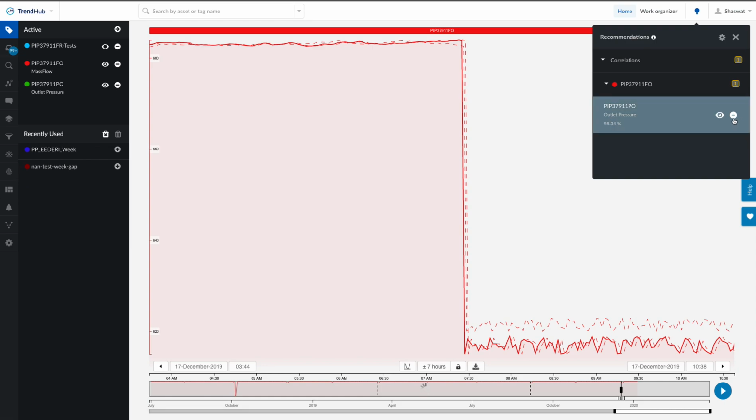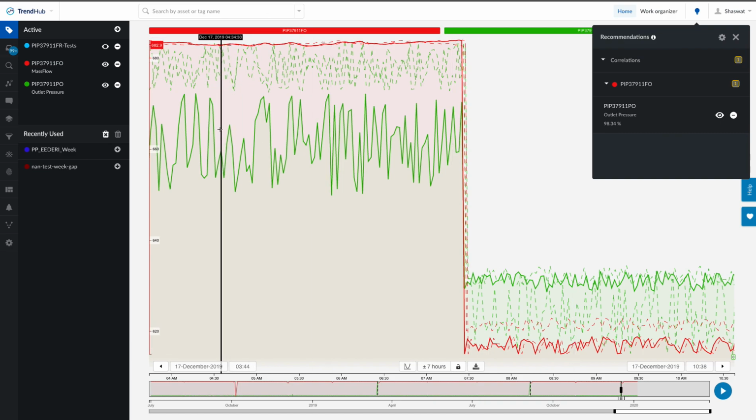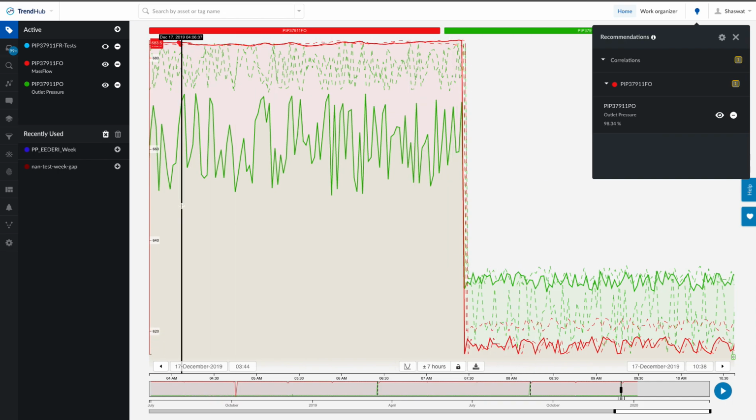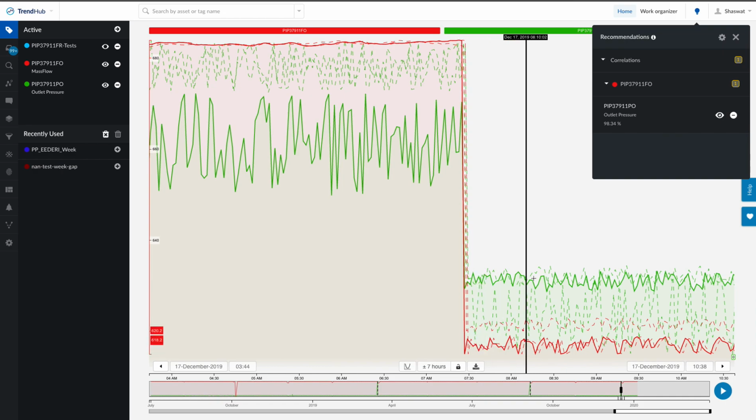So I can bring this pressure here. And as I bring the pressure, you can see in the two events, pressure was a little high and then it dropped kind of low. Versus the third event, we had little lower pressure, and then when it dropped because of the leak, it didn't drop that much relative to the other events.